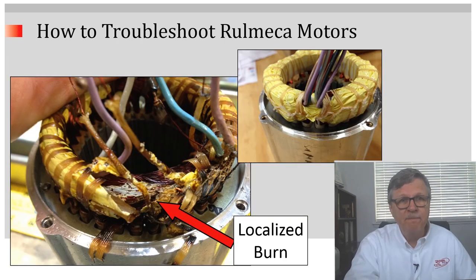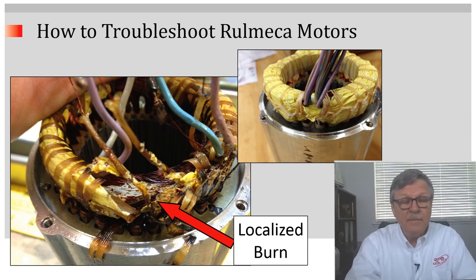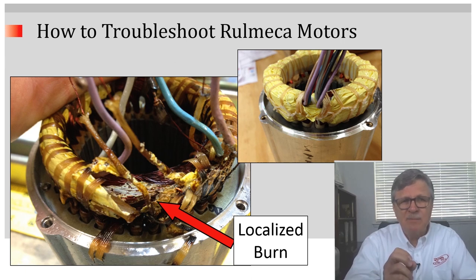Here we see a localized burn, and this is typical of a voltage surge. A voltage surge can occur from a lightning strike or from a resonance-induced voltage spike. A resonance-induced voltage spike will occur when a VFD is located far from a motor and the line is not filtered. A lightning strike or a resonance-induced voltage surge will appear as a very small pinprick of damage on the stator.